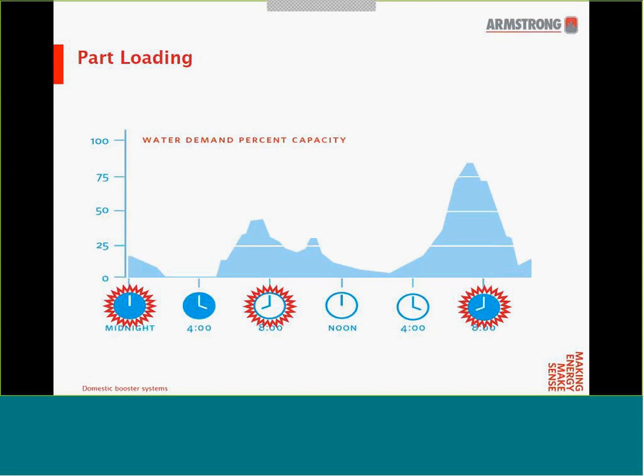Most modern tanks are fitted with a bladder where water enters the bladder, filling up the space in the tank and compressing the surrounding air. The compressed air creates a cushion that can absorb or apply pressure as needed to provide efficient water supply under low demand conditions without operating the pump. Bladders are usually made with NSF rated materials because of potable water requirements. If we monitor a booster system, we notice that throughout the day the demand changes quite drastically — water demand typically peaks in the morning, evening, and midnight hours, with low demand for the remainder of the day. HVAC and plumbing is dominated by part loads.